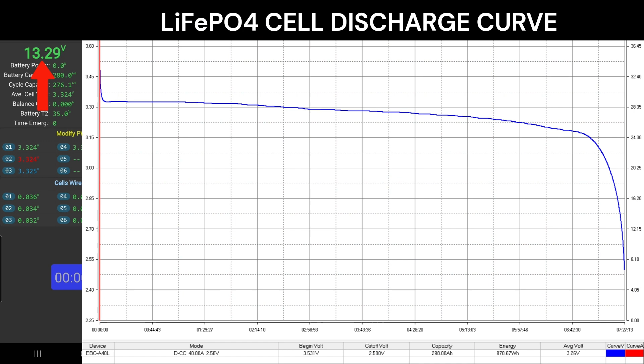Okay, so we're going to turn our breaker on, and what do you guys think it will be? How much current will flow from this battery into this one when this one's at 100% state of charge and this one's at 75%? So there's a 25% disparity. But remember, our voltage is at 13.29, so we're still in the 3.2, 3.3 volts per cell range, which is in the voltage curve of a LiFePO4 cell. We might not see anything until we get down to like 25% or something, because that curve just stays flat until the very end.